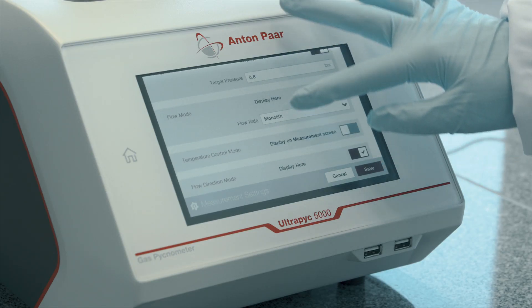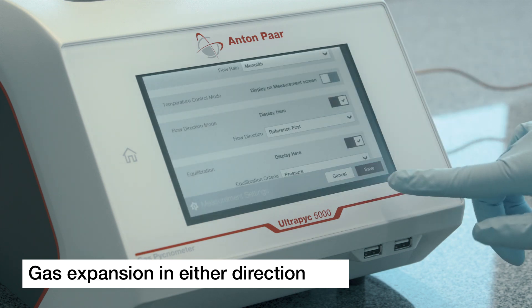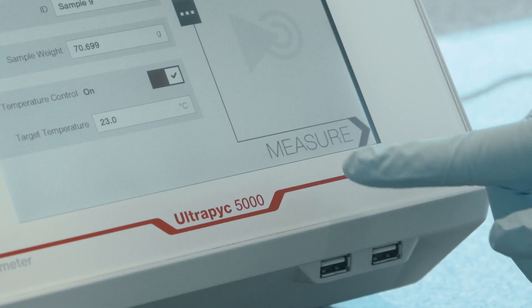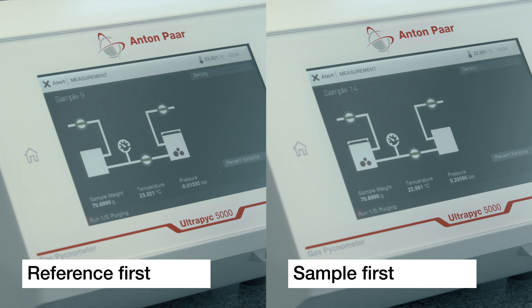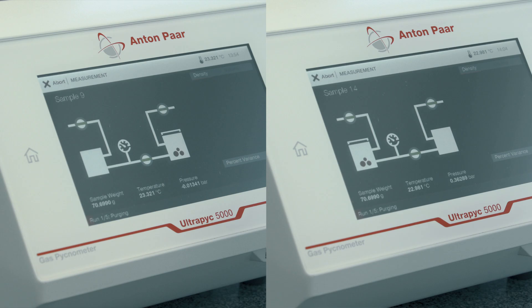The Ultrapyc 5000 instruments feature the unique capability to direct gas flow from the sample chamber to the reference chamber and vice versa. Flowing the gas through the sample chamber first enables you to control the pressure applied to the sample. Selecting the reverse direction and running in powder protect mode virtually eliminates instrument contamination when working with fine powders.